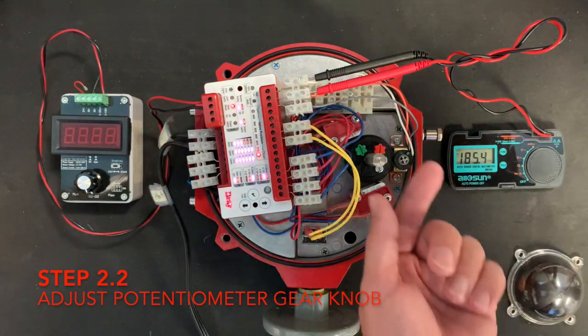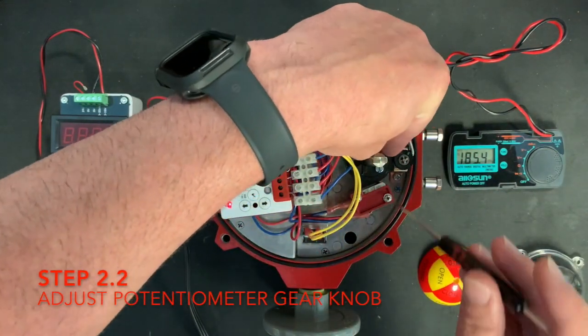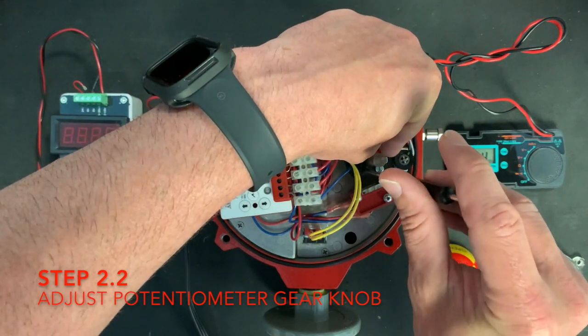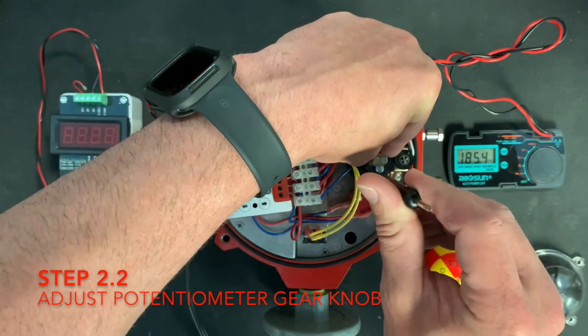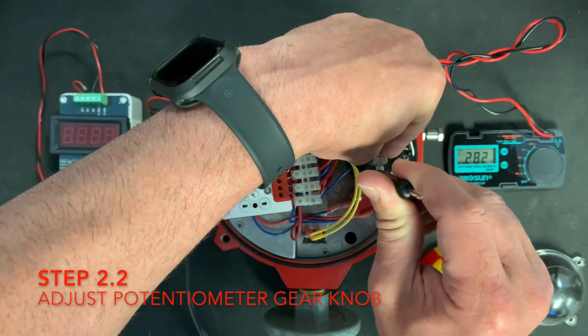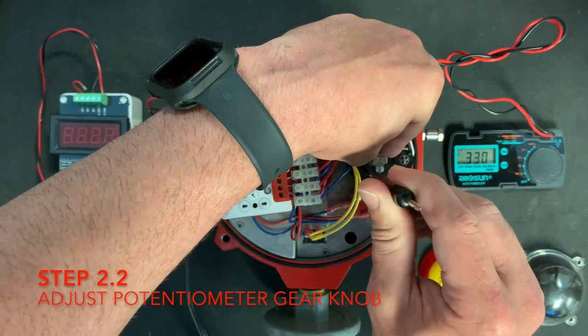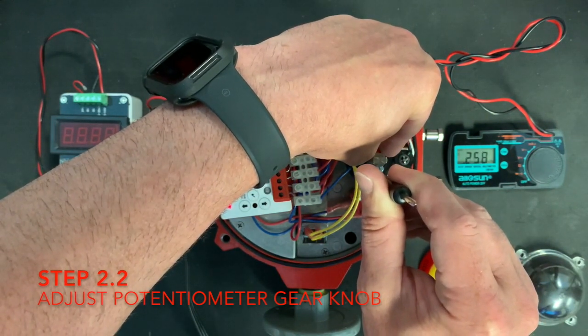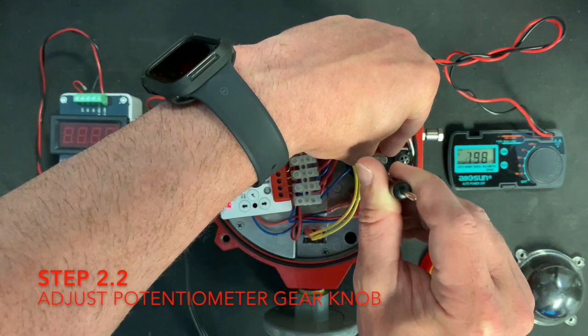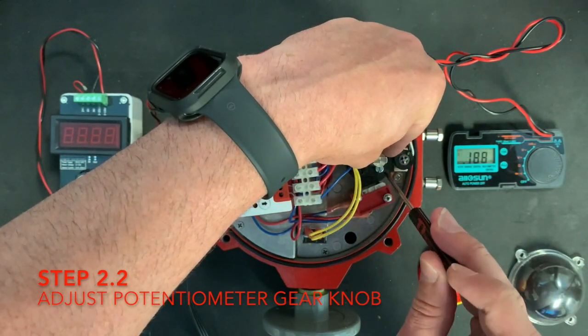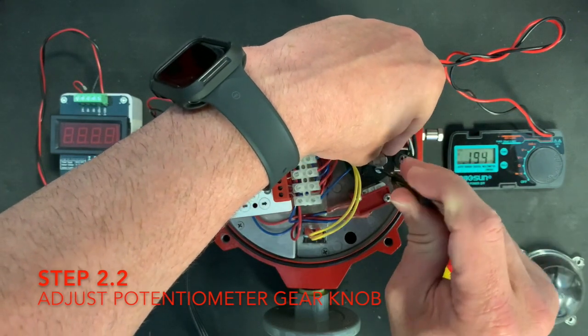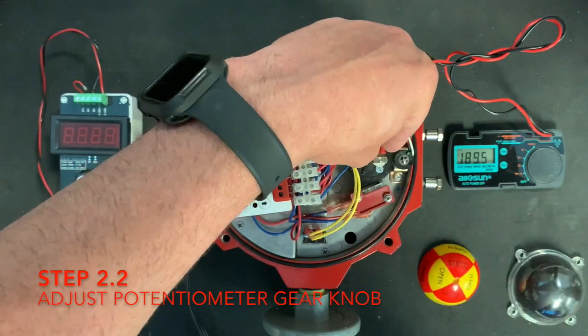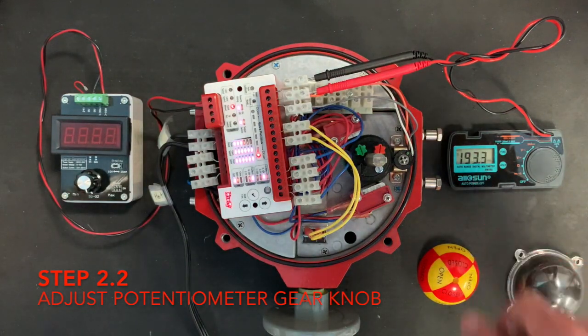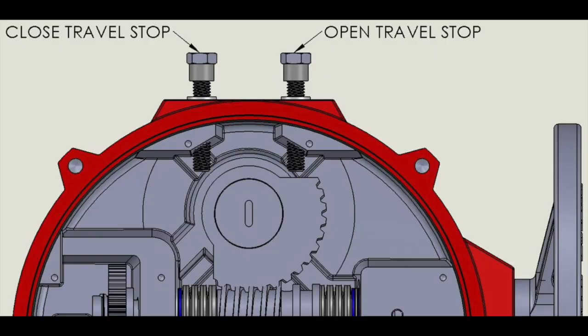Rotate the black potentiometer drive gear adjustment knob with a flathead screwdriver until the multimeter VDC measurement falls within 0.16 to 0.21 VDC in the closed position. Note: make gentle contact when bringing the mechanical stop in contact with the output gear. When tightening the nut, use 2 wrenches, one to hold the bolt in place and one to tighten the nut. Do not drive the mechanical stop into the internal segment gear and crack the plastic washer.